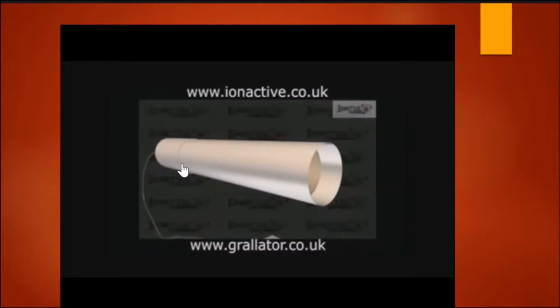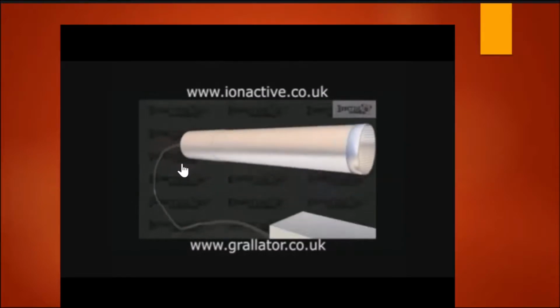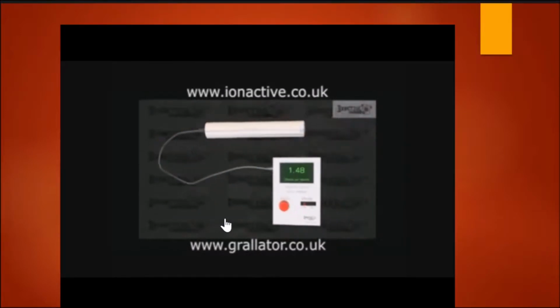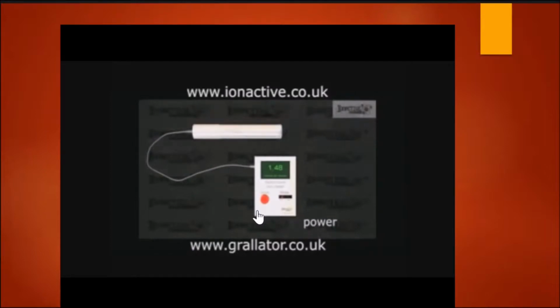This tube guard can be open at the end or be covered by an end cap energy filter to change the energy and particle sensitivity of the device, or, if a carefully calibrated design is used, allow for ambient dose measurements rather than ambient count measurements to be made. The wires connect the tube to the control electronics, which supply power, perform the counting operations, and provide other functions such as conversion from counts to dose, data logging, data averaging, and driving the display.